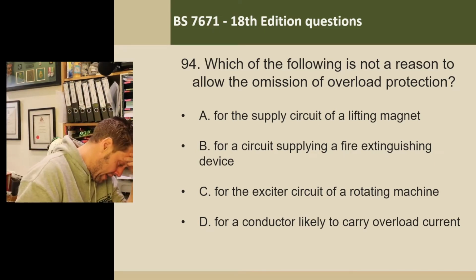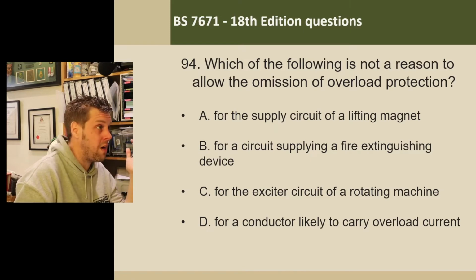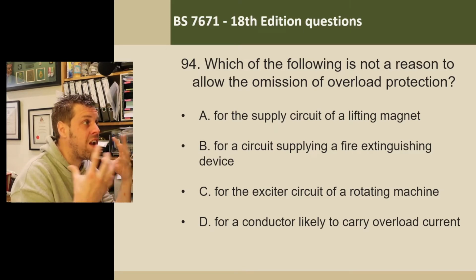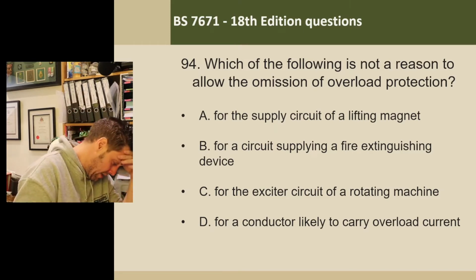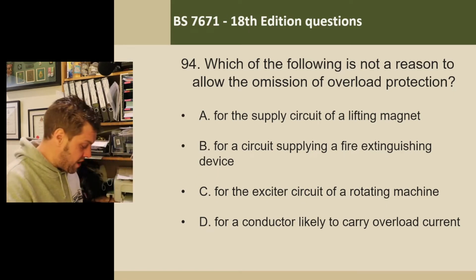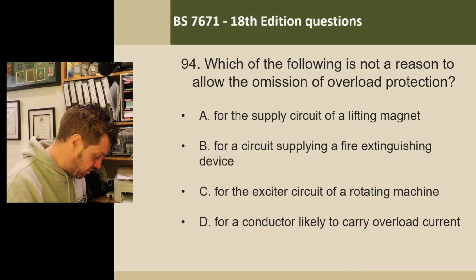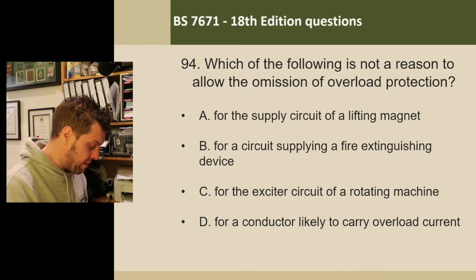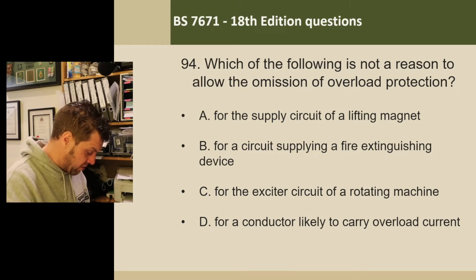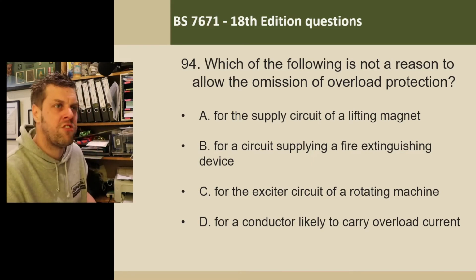So as I skim down it - and I want you to do this at home too - because I'm going through the questions in a logical process, I get to 433.3.3. It's called the omission of devices for protection against overload for safety reasons. It says the omission of devices for protection against overload is permitted for circuits supplying current using equipment where unexpected disconnection of the supply would cause danger.